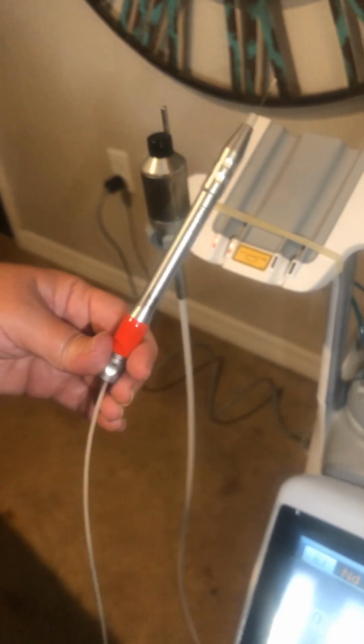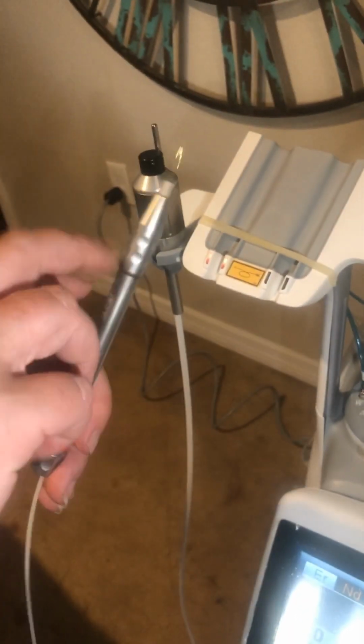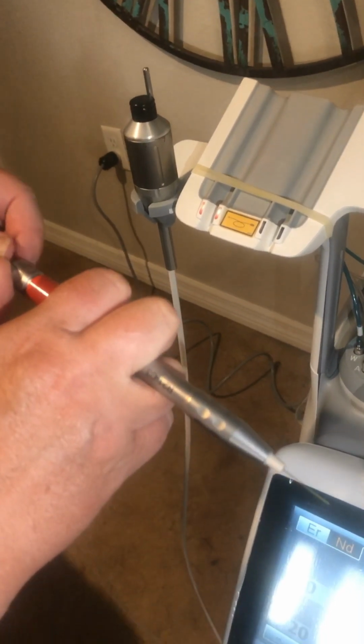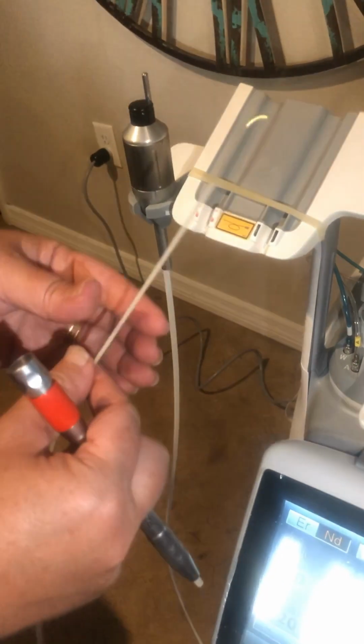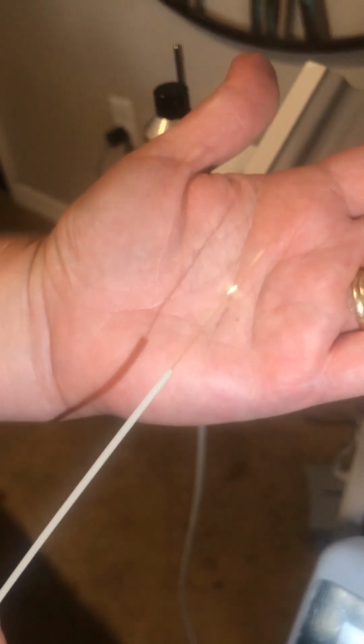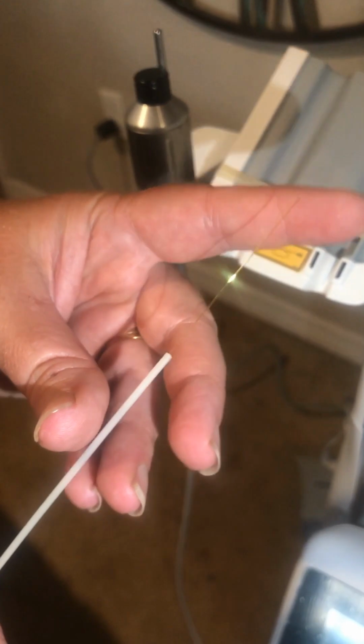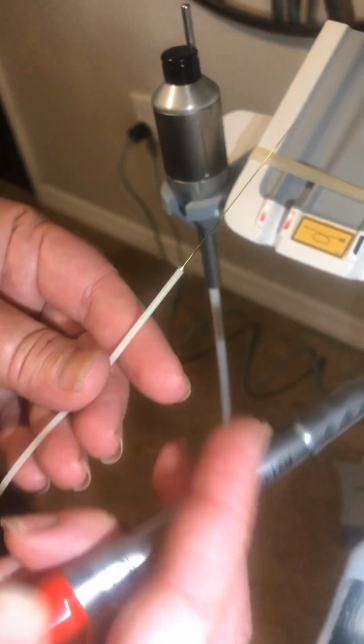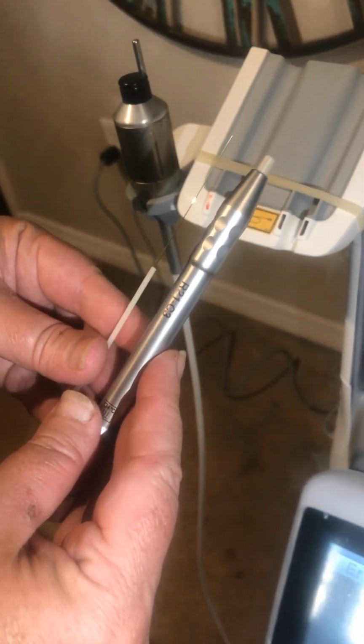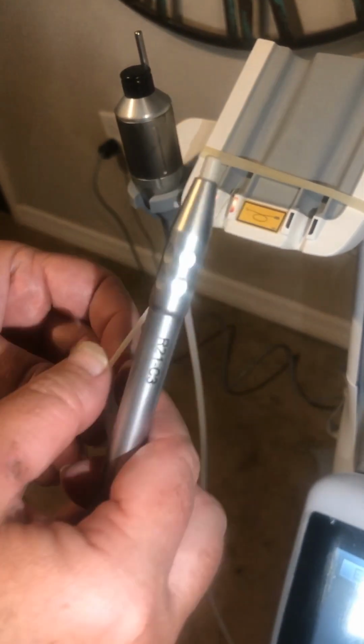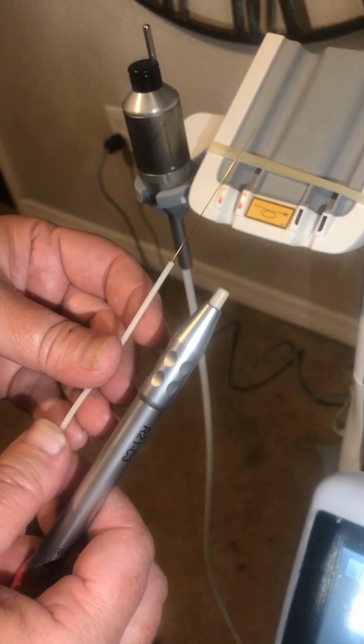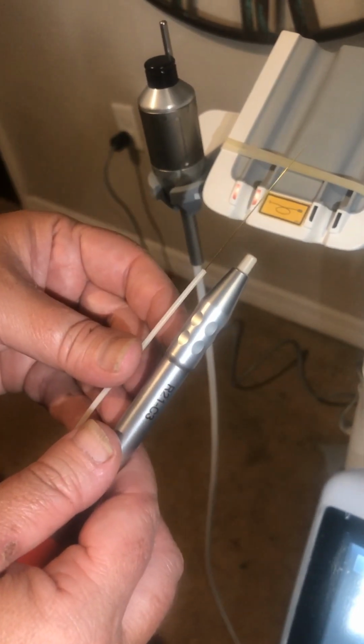And I'm going to show you in a separate moment here how to actually strip the fiber and cleave it, because this is what the fiber looks like when it's not in the handpiece. It's basically a glass fiber inside a rubberized tube. And you want to have about that much of the fiber, I don't know if you can see that very well, exposed because there's a portion of the handpiece where it's going to narrow, and as it does, you need to make sure that the plating is off so that it will be able to reach out the end of the handpiece, okay?